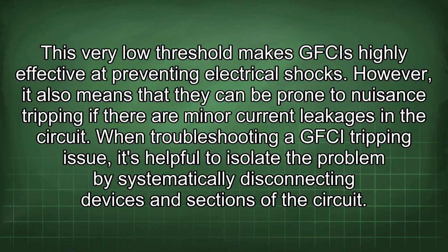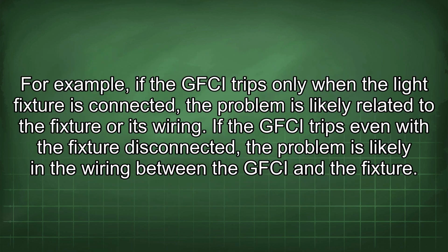When troubleshooting a GFCI tripping issue, it's helpful to isolate the problem by systematically disconnecting devices and sections of the circuit. For example, if the GFCI trips only when the light fixture is connected, the problem is likely related to the fixture or its wiring. If the GFCI trips even with the fixture disconnected, the problem is likely in the wiring between the GFCI and the fixture.